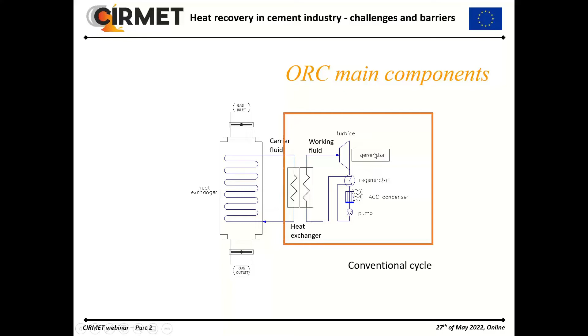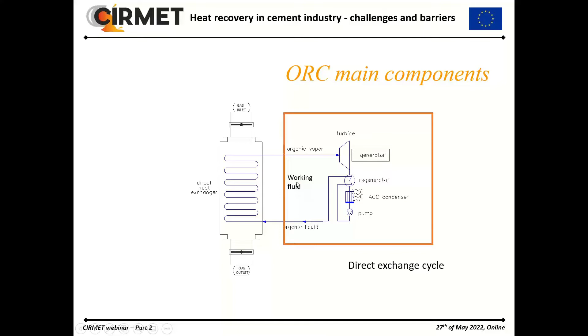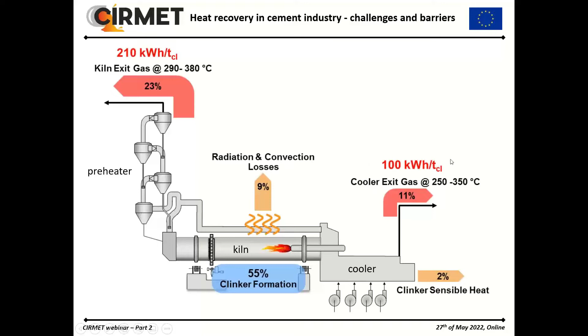That's a conventional cycle. In the direct cycle, we eliminate one of the exchangers, so we increase the efficiency of the system. In a burning system, we obtain more or less 210 kilowatt-hours per ton of clinker from the preheater and 100 kilowatt-hours per ton of clinker from the cooler. In a medium cement factory with an output of 2,000 tons of clinker per day, we obtain 310 kilowatt-hours per ton of clinker.